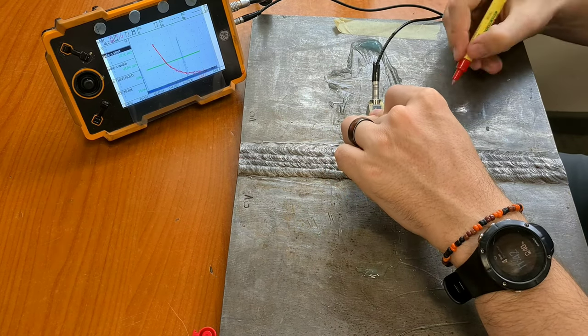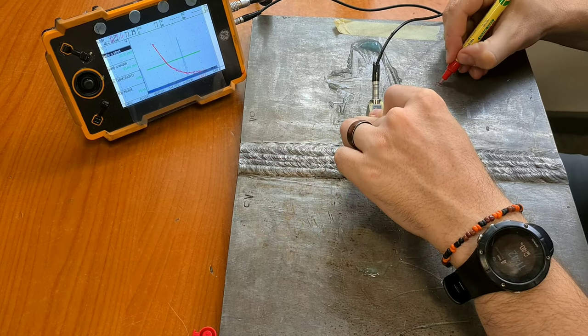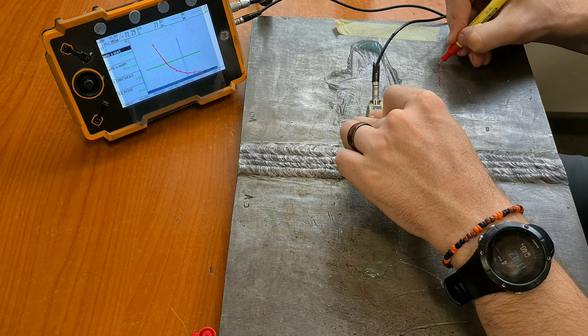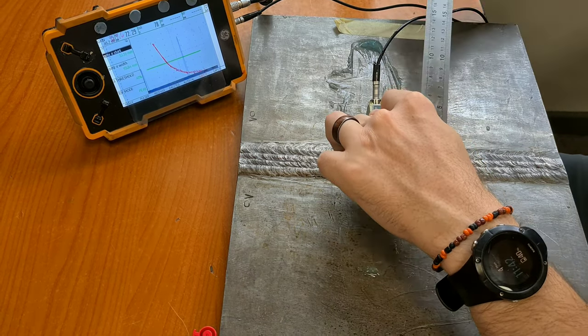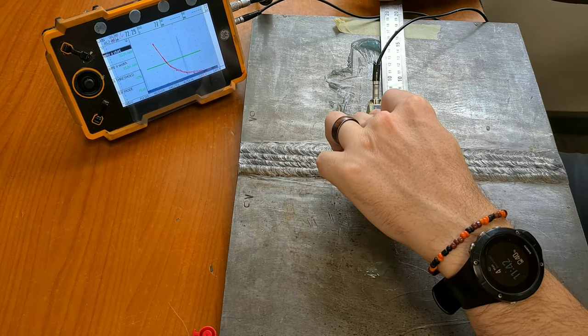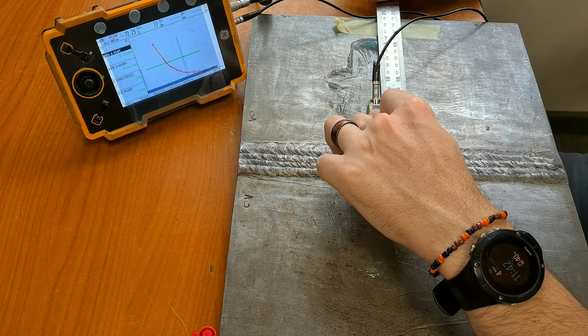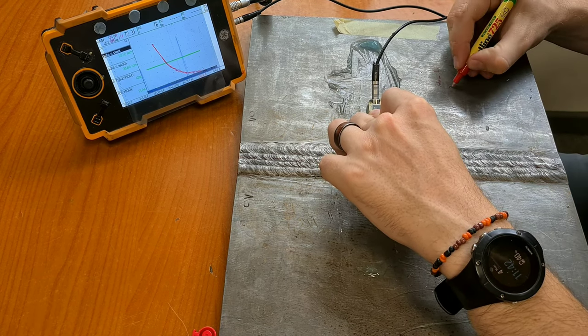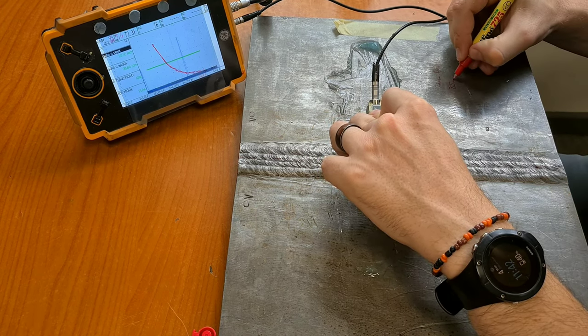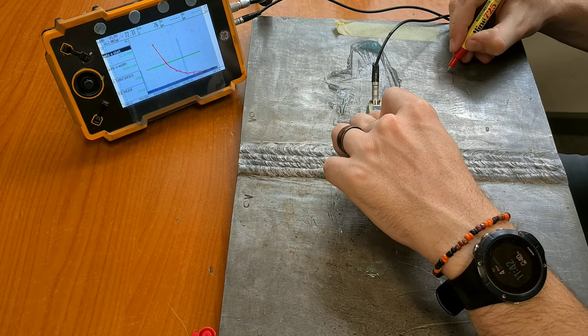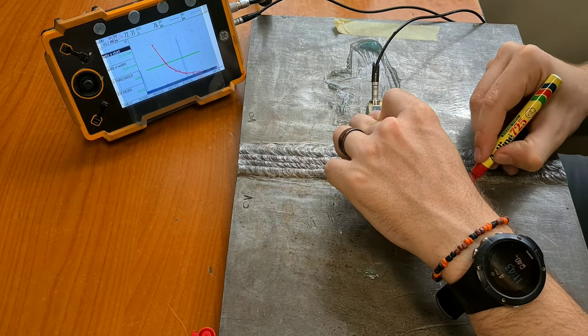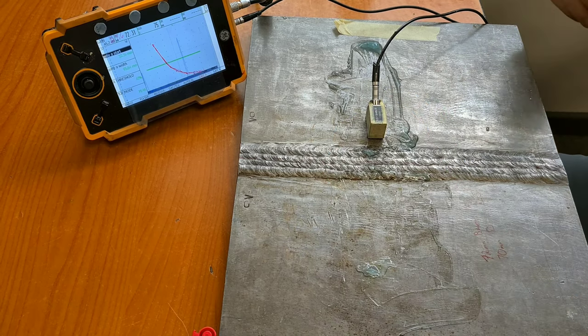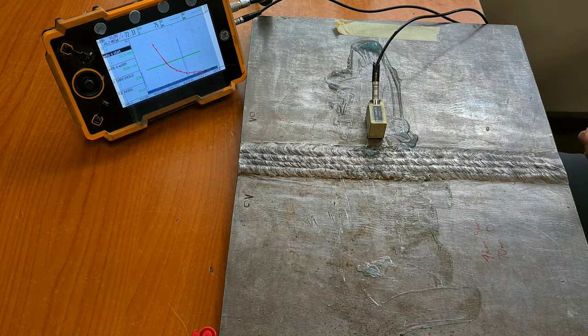This is about 72 millimeters of beam as well, and the distance from center though is a lot less. From center to where the sound exits my probe is 35 millimeters. And remember, this probe that we're using is a 45 degree probe from each side and it's got a big response. Let's see how it plots out.